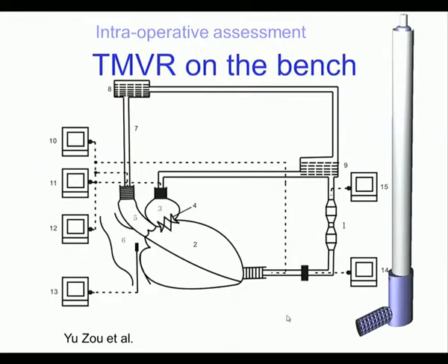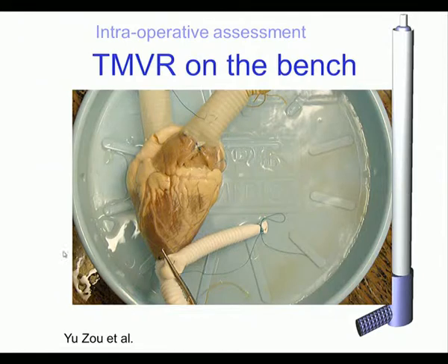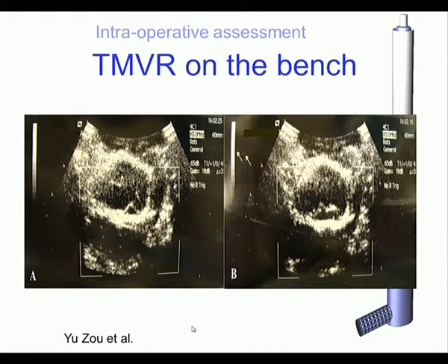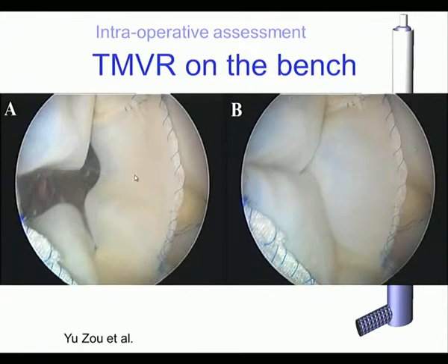We have also looked at a similar approach for the mitral valve on the bench. Dr. Yu has done this work. The heart is connected to several grafts including one to the left atrium so that the valve can be brought in from the left side in a transparent fashion. There is some noise in the water bath which is not the case in the clinical setting, but you may recognize that there is a valve implanted here. You can see the leaflets, and here the valve is open. Of course in the water bath it is easy to see this with endoscopy.